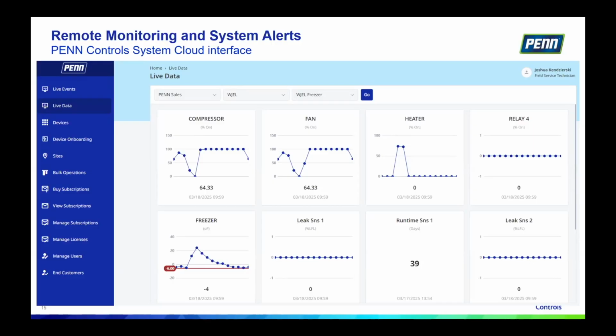And then, of course, with the freezer temperature input, we're monitoring that as well in the bottom left to make sure it's within the set point range. And then we have a couple of A2L sensors connected as well that are showing no leaks over the last 30 days. And then, of course, you can set up alarms for any of these points to go to an email inbox or text as well.